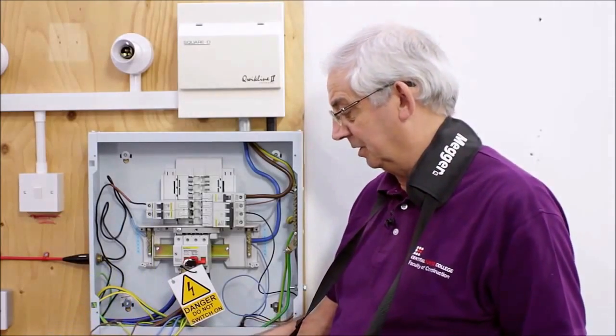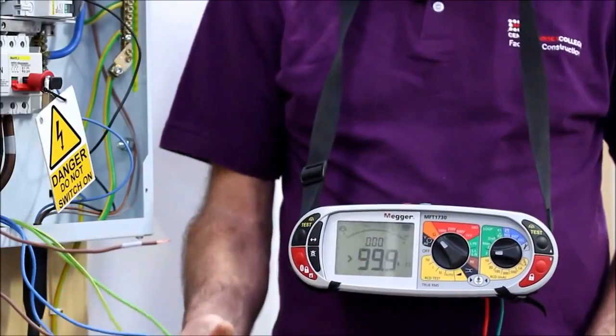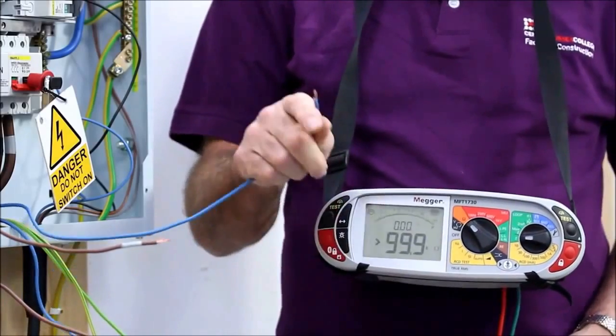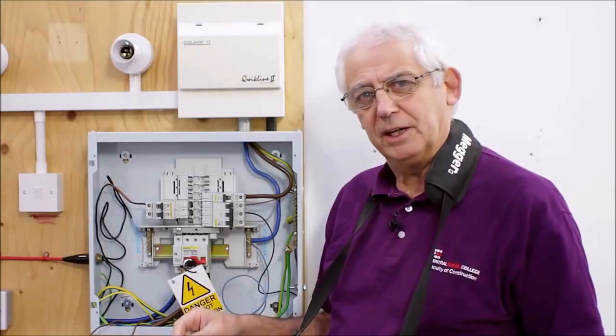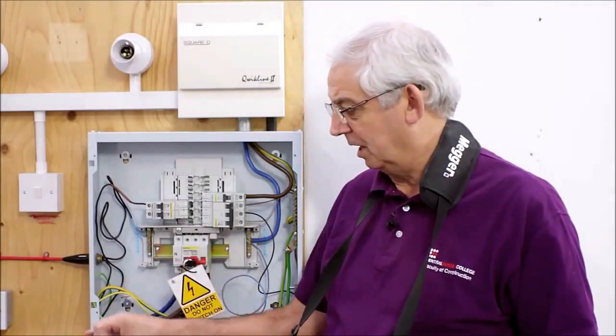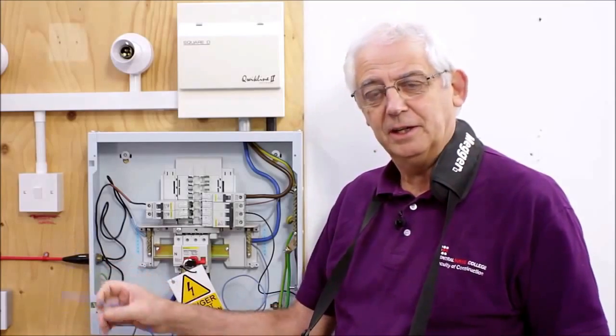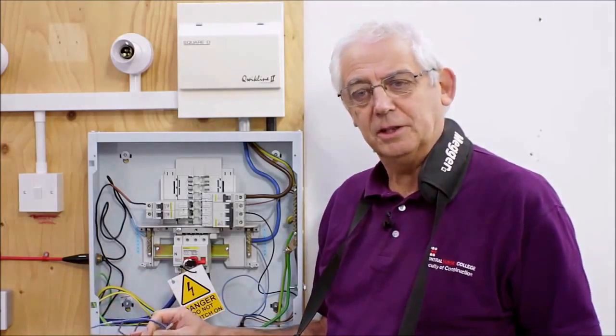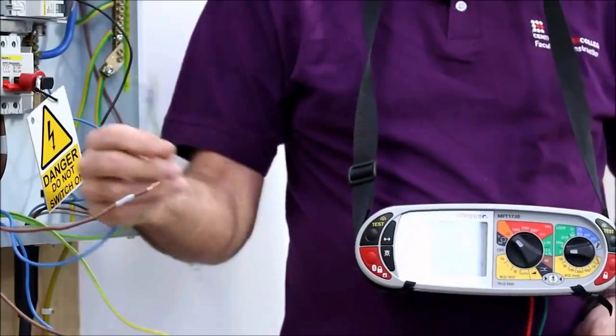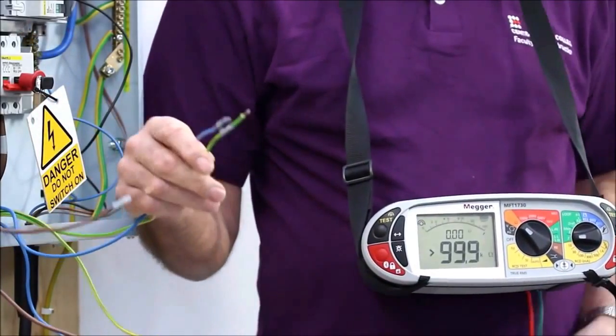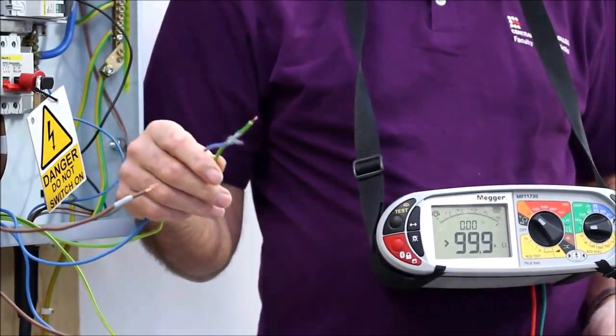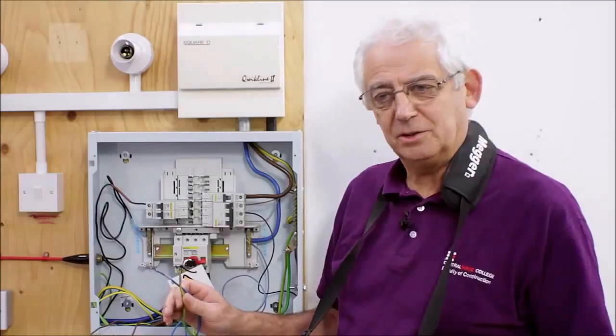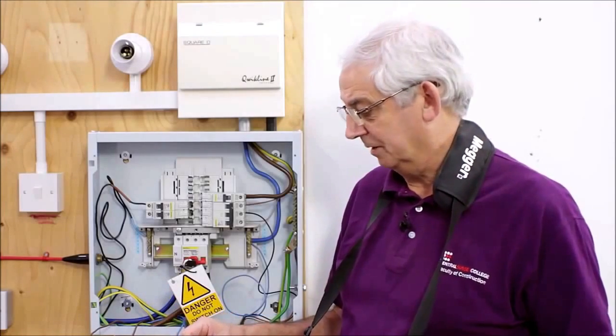These are our ring circuit leads or cables, and they're identified. It's very important that each end of the ring is identified so that we know which one goes to the first socket and which ones come from the last socket. These are just identified with a bit of grey tape. Most people can use tape or numbers or whichever way you prefer. As long as they're identified, it doesn't matter.